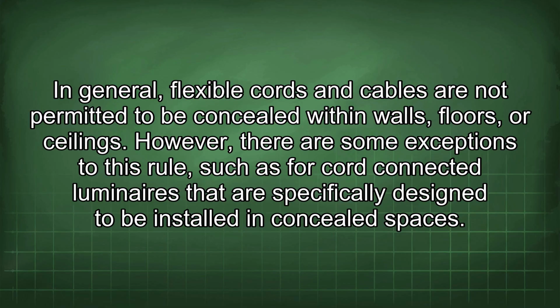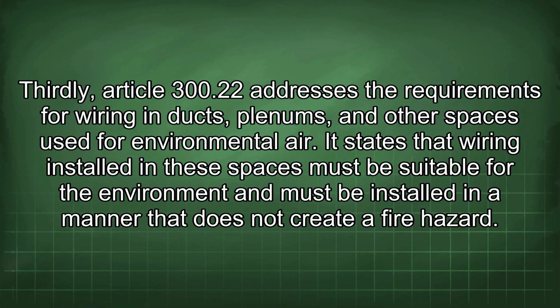However, there are some exceptions to this rule, such as for cord-connected luminaires that are specifically designed to be installed in concealed spaces. Thirdly, Article 300.22 addresses the requirements for wiring in ducts, plenums, and other spaces used for environmental air. It states that wiring installed in these spaces must be suitable for the environment and must be installed in a manner that does not create a fire hazard.